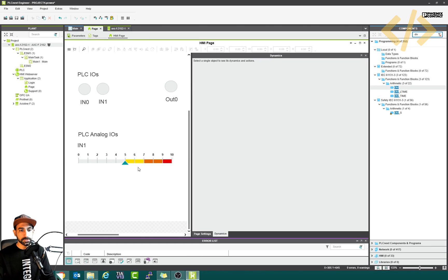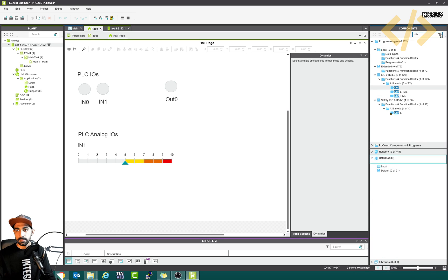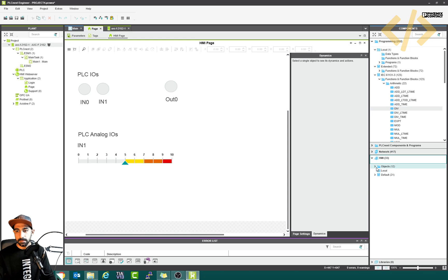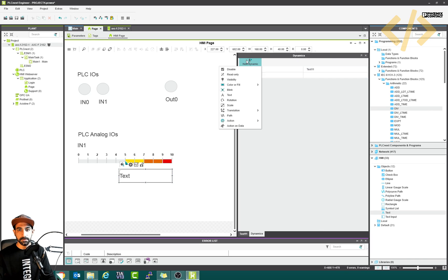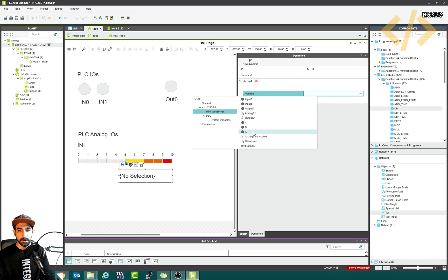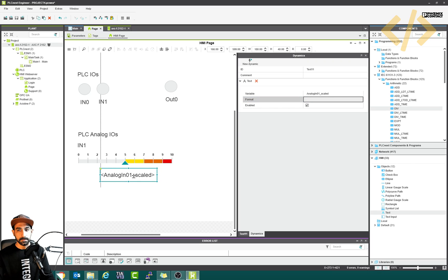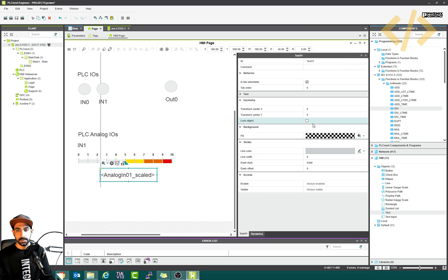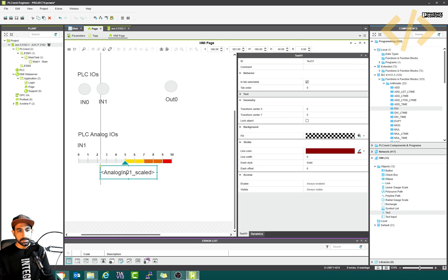I go back to my HMI. I want to show the scaled value here — it's quite easy. In the object panel, find 'text' and bring it here. This is a text object, but we need a dynamic text, not a static one. So add new dynamics, then go to 'text' since we're displaying a number. Click text and give the variable from the server: analog 01 scaled. You can see the values mentioned. If you want, you can also change the color of the text.